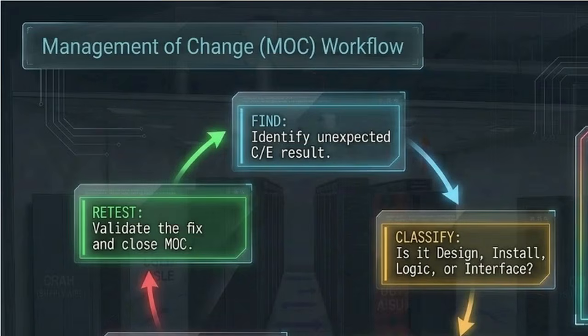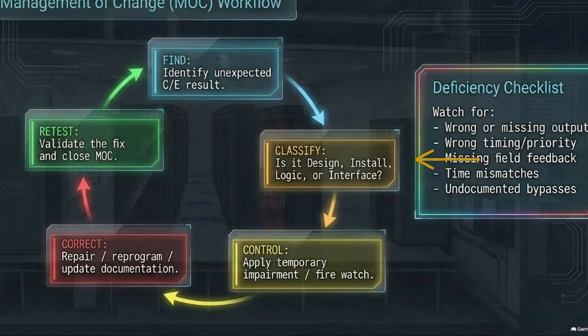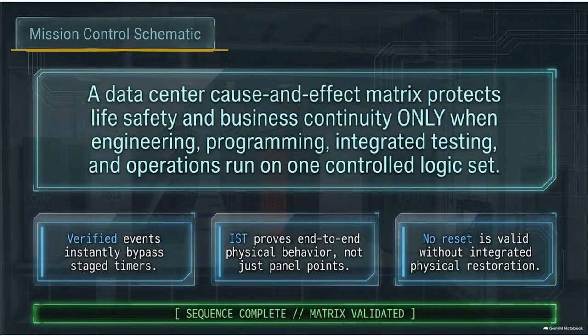If testing or operations reveal an unexpected result in the matrix, it must go through this management of change workflow. The team must classify the deficiency, apply impairment control, correct the logic, and perform a full retest to close the loop. Looking at this final schematic, we see the core takeaways. Verified events bypass timers. IST proves end-to-end physical behavior, and no reset is valid without physical restoration. Life safety and business continuity are only protected when engineering, programming, and operations run on one unified logic set.